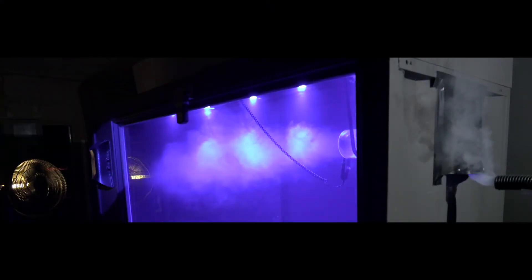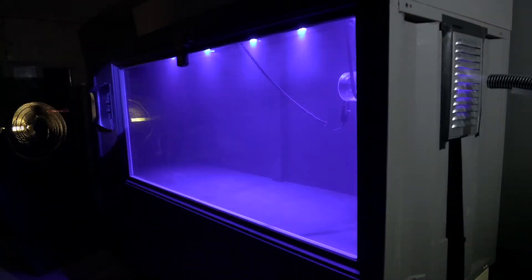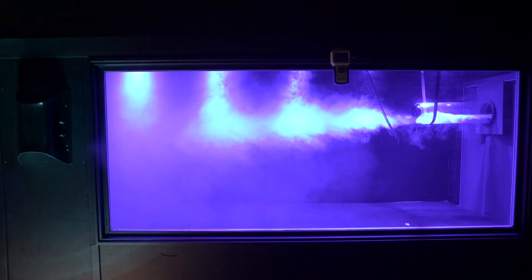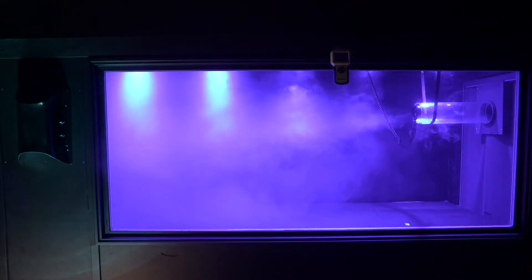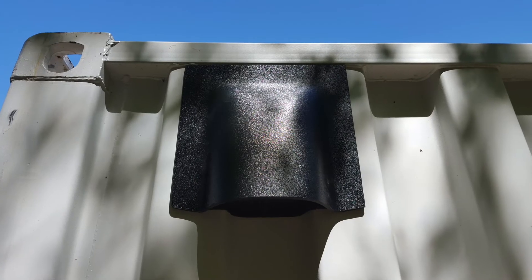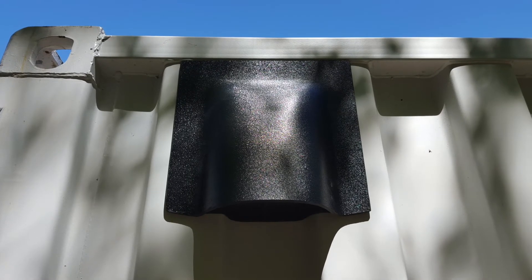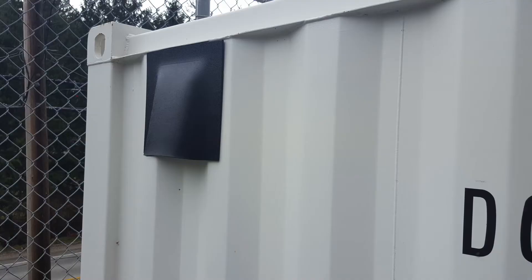It can be advantageous to install the intake near the ceiling. The low pressure created by the exhaust driver draws in the outside air easily through a non-restrictive intake. We recommend a hooded-style intake as they have less of a chance of pulling in rain or mist compared to louvered vents.